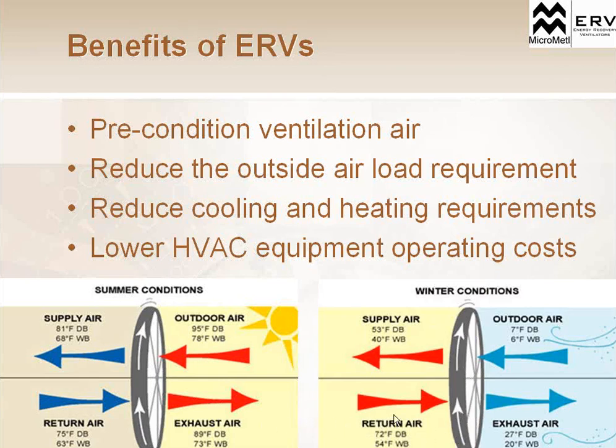In the winter application, we've got our exhaust air from the building at 72 degrees, which is an average set point. We've got an outside air temperature of 7 degrees, which is a typical temperature for the Chicagoland area. So the return exhaust air from the building is transferred on the wheel to the outside fresh ventilation air coming in the supply. And we go from 7 degrees of outside air, picking up that sensible energy, to 53 degrees.